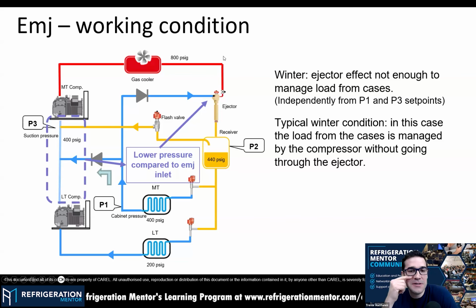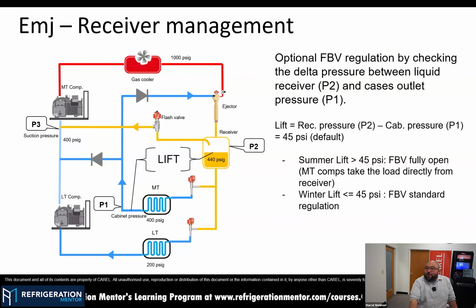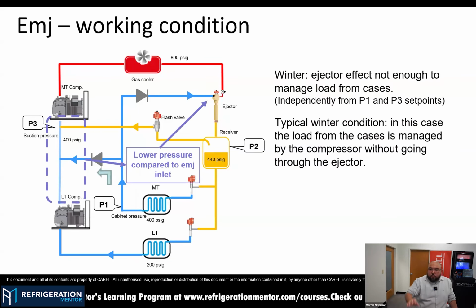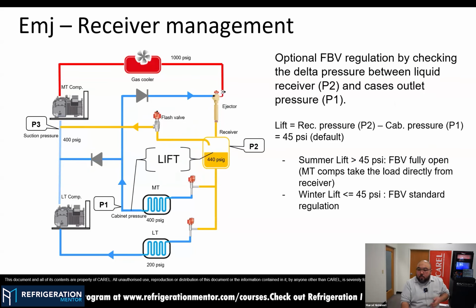Okay, let's keep going. With different conditions, the ejector will be adjusting for different behaviors. When it comes to the ejector effect, we are maximizing efficiency with the HPV valve. And what about the flash gas? What is the role of the flash gas in this ejector world? It should operate with a fixed set point, with different ones.